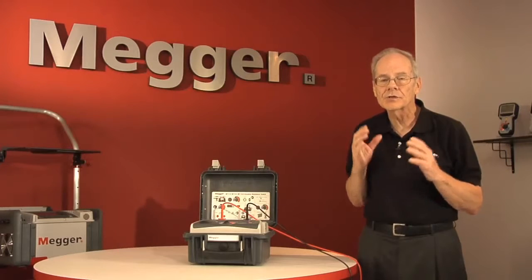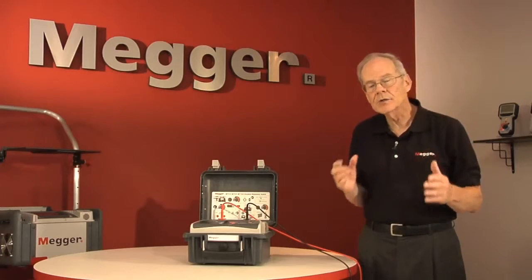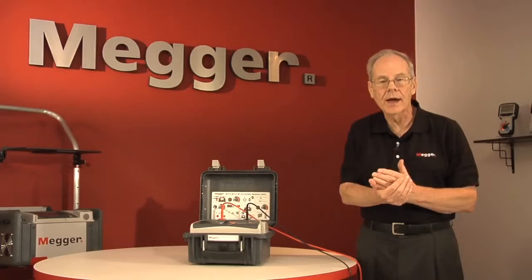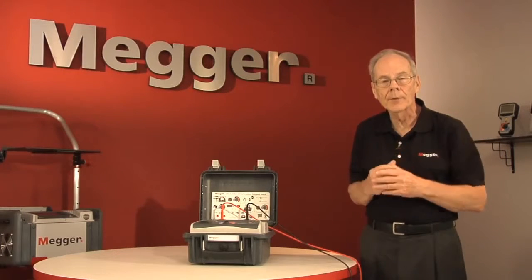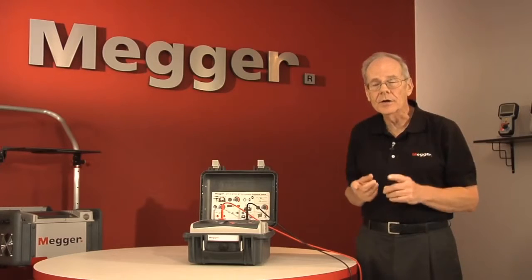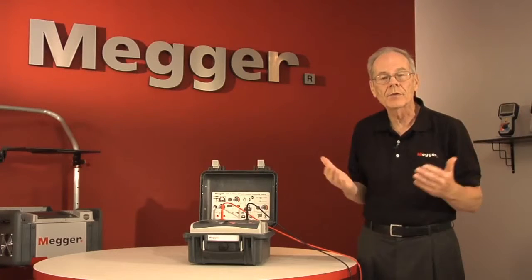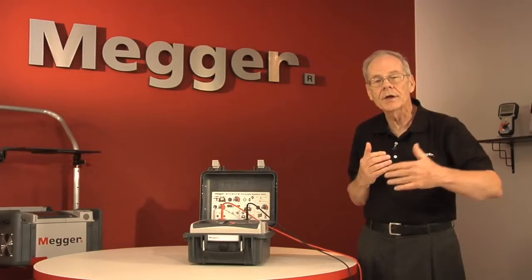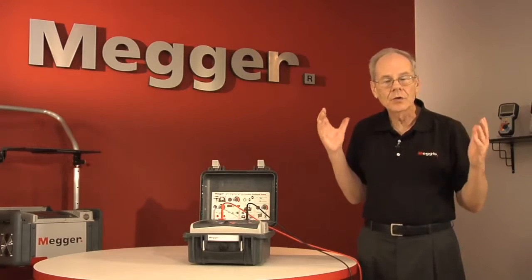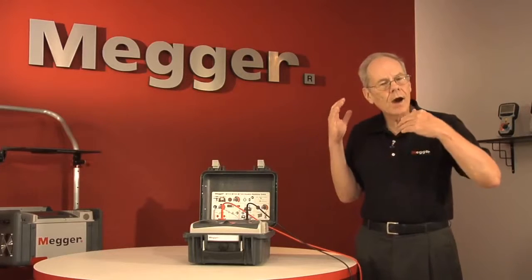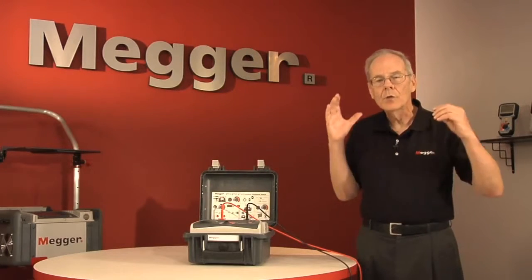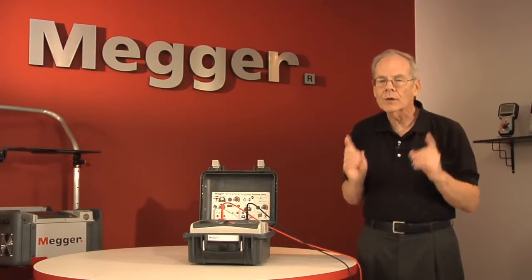Temperature affects insulation notably and consequently has to be taken into account, and for record purposes typically adjusted to a common temperature base. And thirdly, you end up with a number. This could be anything covering an enormous range. On good equipment, it can range from megohms to teraohms. So the operator is now left with the task of interpreting what that number means.